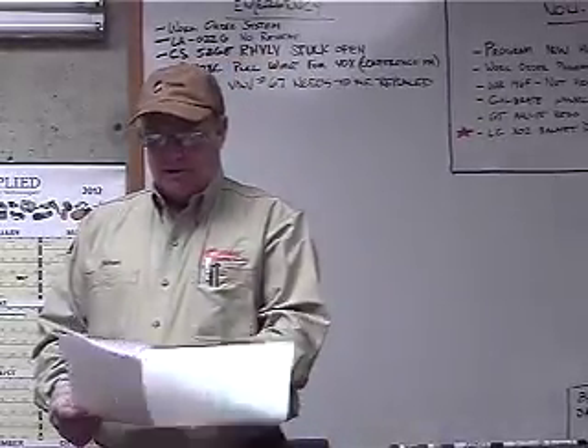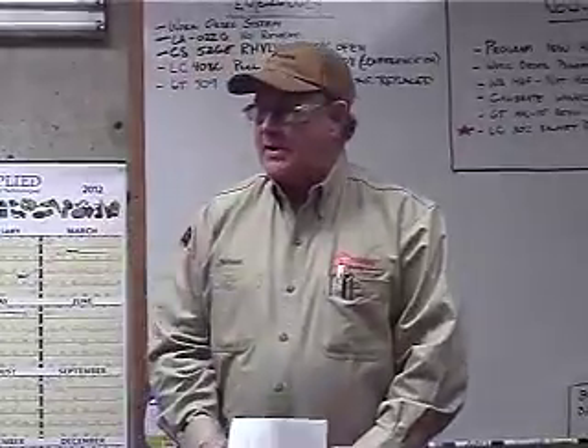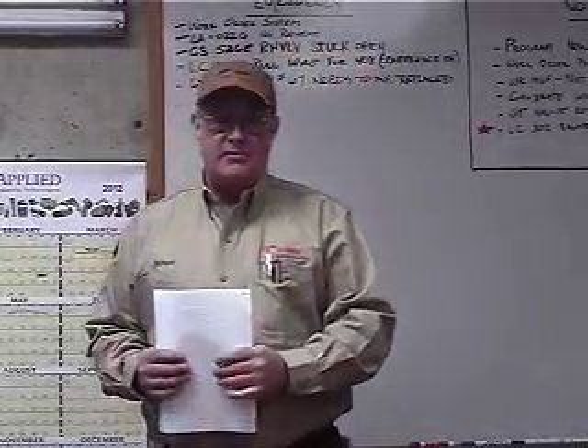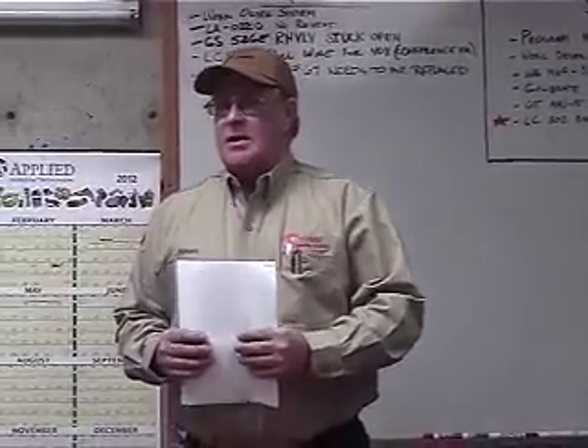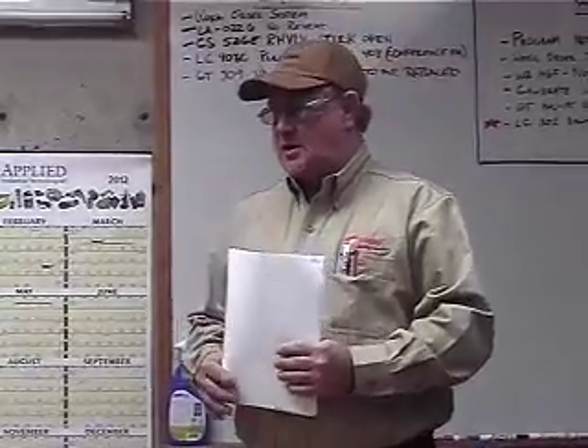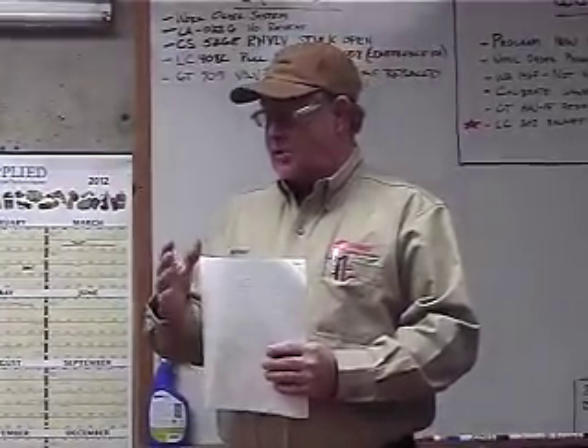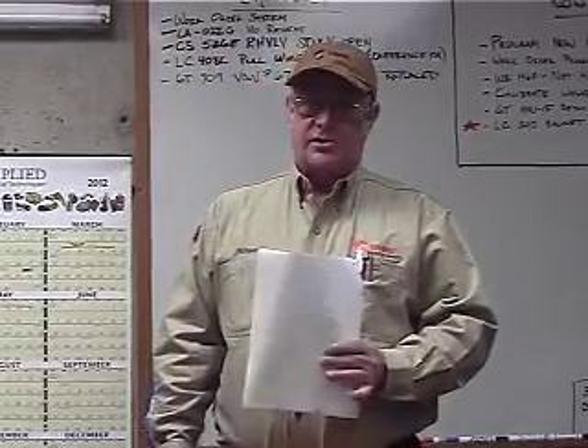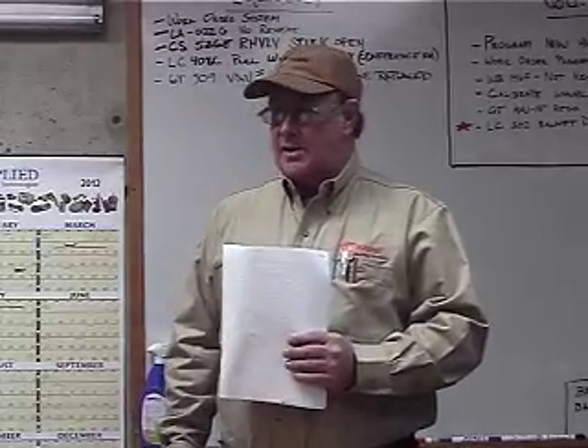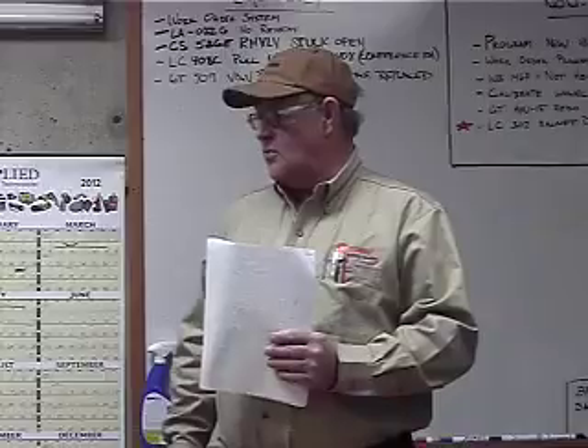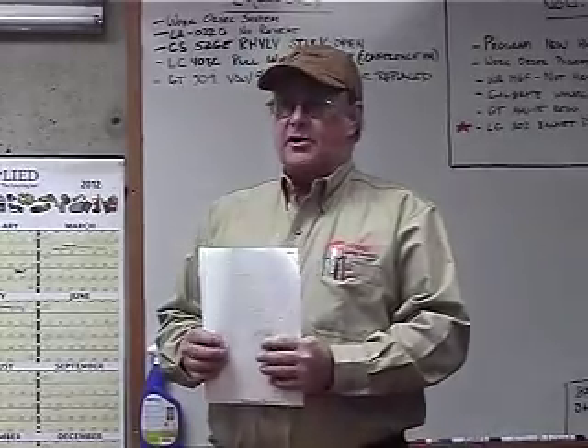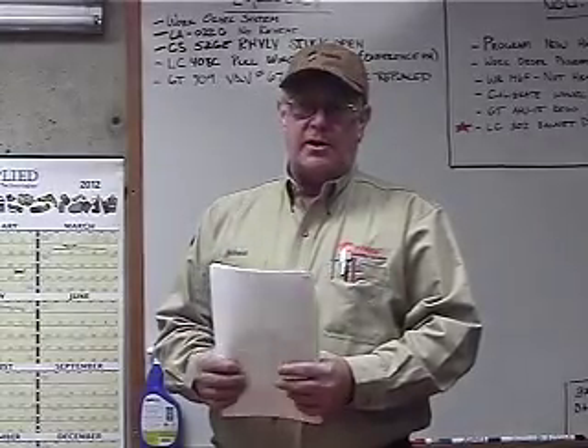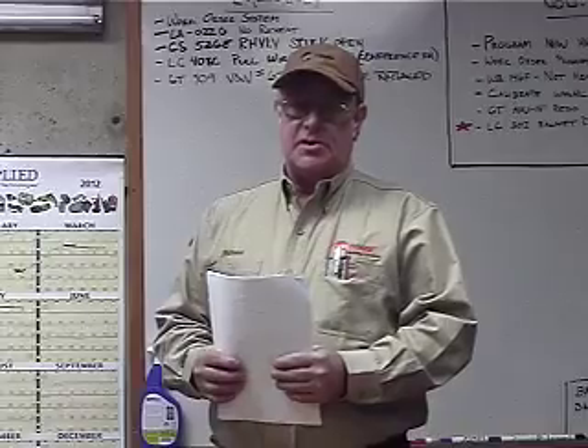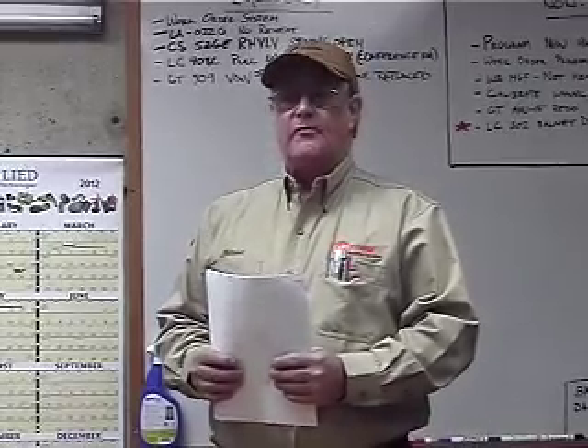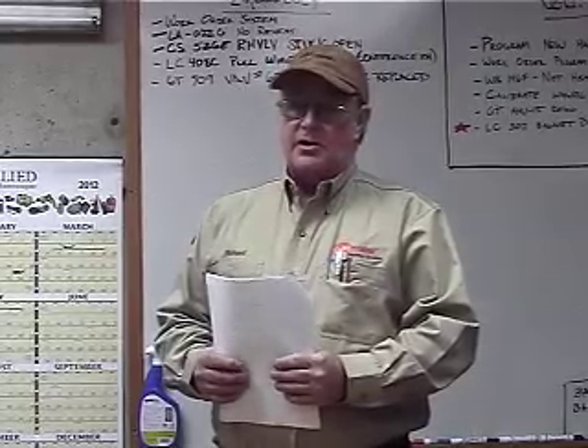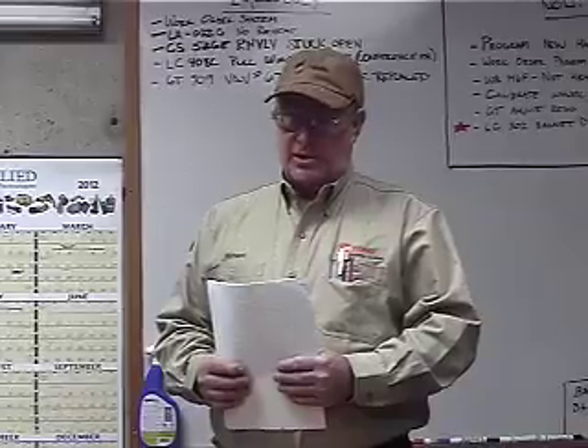I'm here to give you a little bit of training on your chillers outside, or your new chiller. I see quite a few new faces that I haven't seen before. How many people in here actually understand how the chillers operate, or this new Trane chiller? In general? Okay, what I'll do is go through and give you how the refrigeration cycle works on these chillers. The refrigerant in this chiller is R123. That's a low pressure refrigerant, so your suction pressure very seldom goes into a positive pressure. Your condensing pressure will get up to about 15 psig.